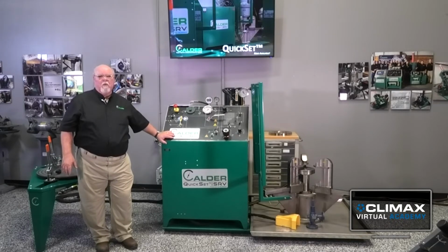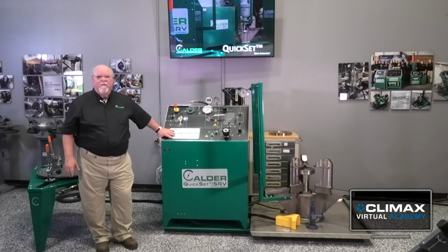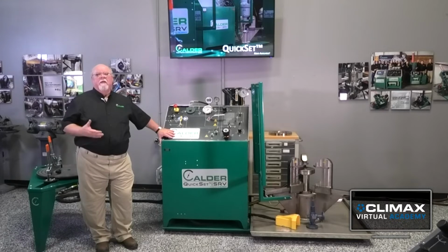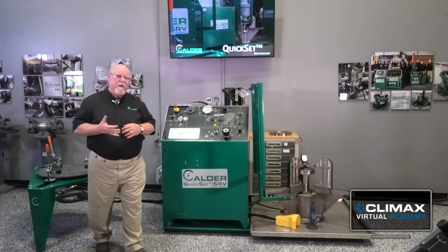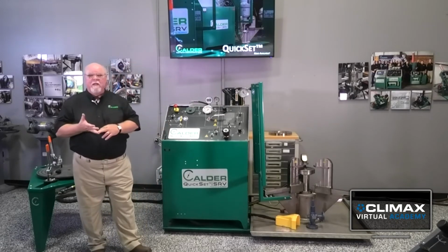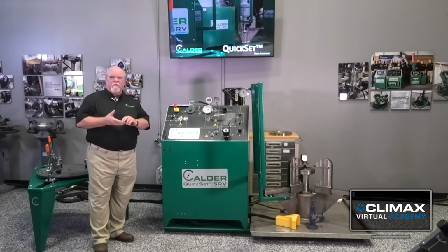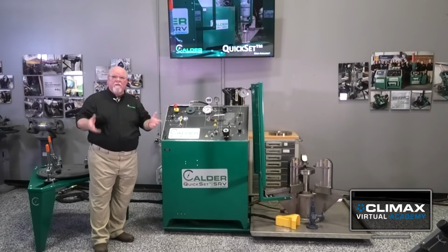One of the options is a data acquisition system that comes along with this and can monitor and record the pressure for testing. It also comes with a bubble counter for seat leakage, the API 527 seat leakage capability. The data acquisition system also provides a back pressure test capability, bellows testing, and also just back pressure testing directly. So we have four different tests that the data acquisition system can do right out of the box.